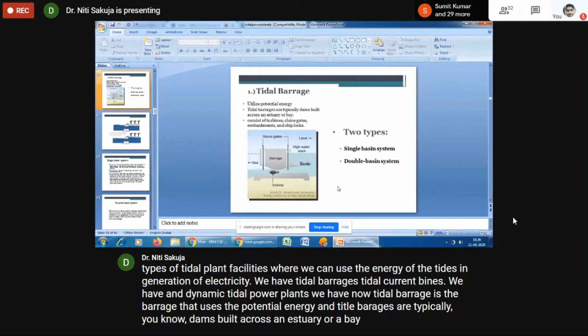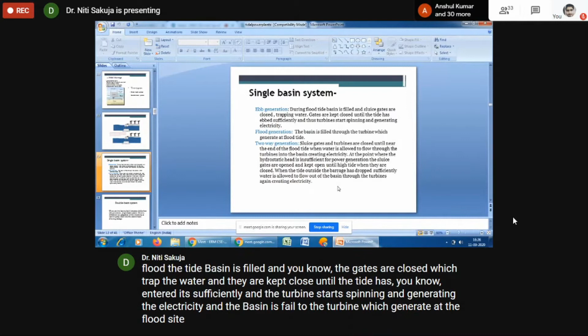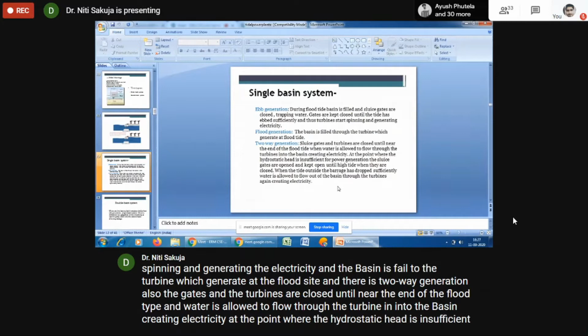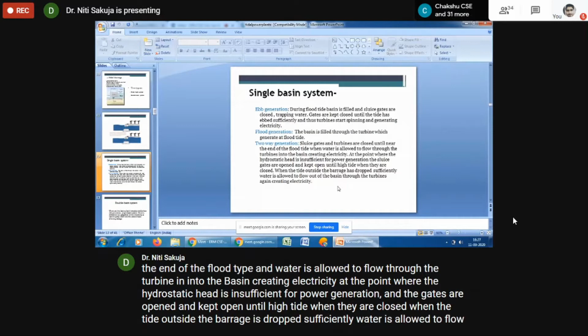Now, what is a single basin system? During the flood, the tide basin is filled, and the gates are closed, which trap the water, and they are kept closed until the tide has entered sufficiently, and the turbine starts spinning and generating electricity. The basin is filled through the turbine, which generates at the flood side, and there is two-way generation also. The gates and the turbines are closed until near the end of the flood tide, when water is allowed to flow through the turbine into the basin, creating electricity. At the point where the hydrostatic head is insufficient for power generation, the gates are opened and kept open until high tide, when they are closed. When the tide outside the barrage has dropped sufficiently, water is allowed to flow out of the basin through the turbines, again creating electricity with the pressure.